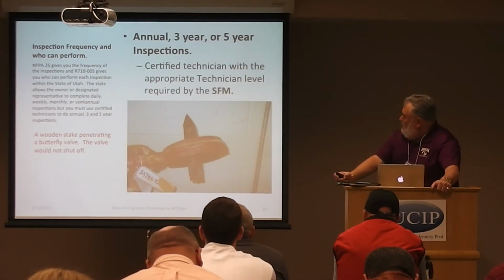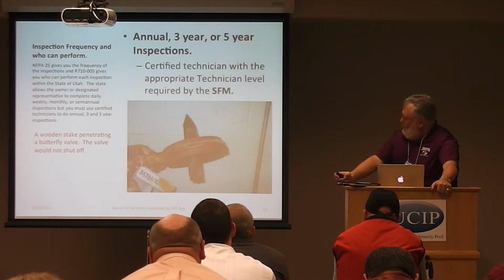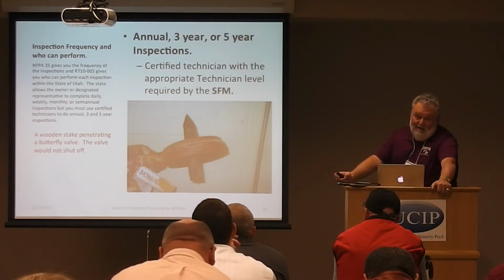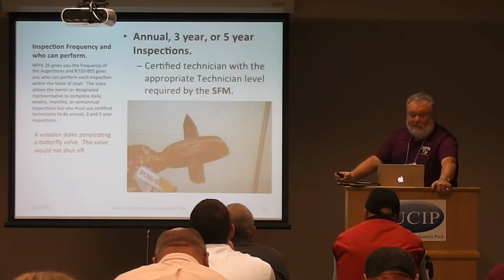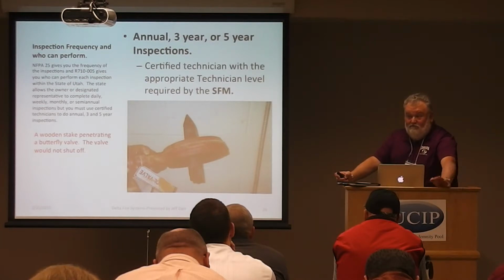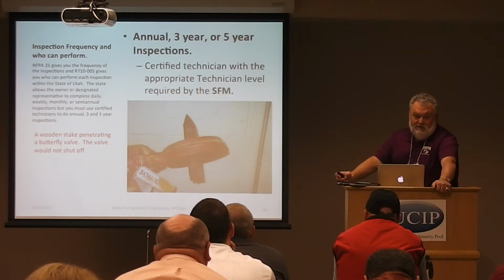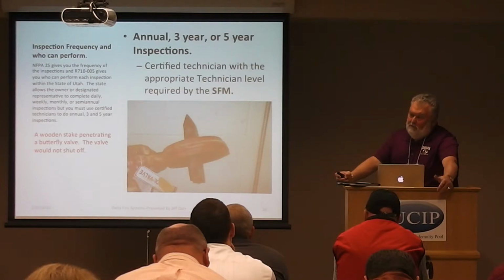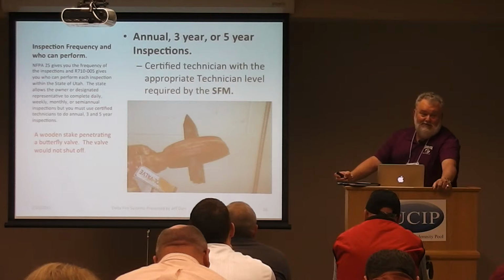And here we have another example, and I could not believe it when I saw this picture: that's a wooden stake right through the butterfly valve. They couldn't figure out why they couldn't get the system to shut off, and pretty obviously that's why. The underground was probably flushed correctly when it was installed, but over time, every time something's opened and closed and water's flowing, it's picking up whatever debris is in there, and that just happened to get lodged in that valve.